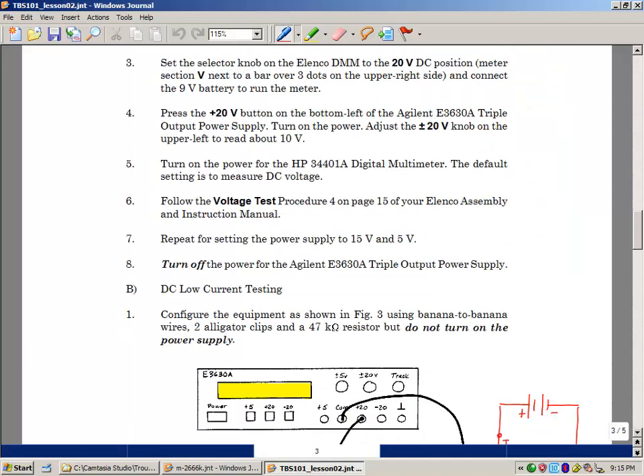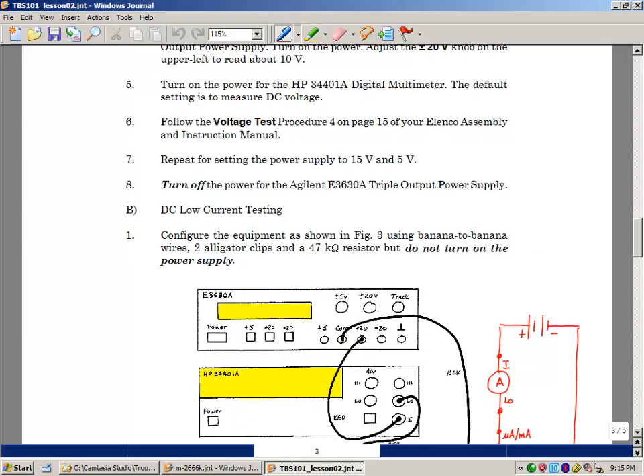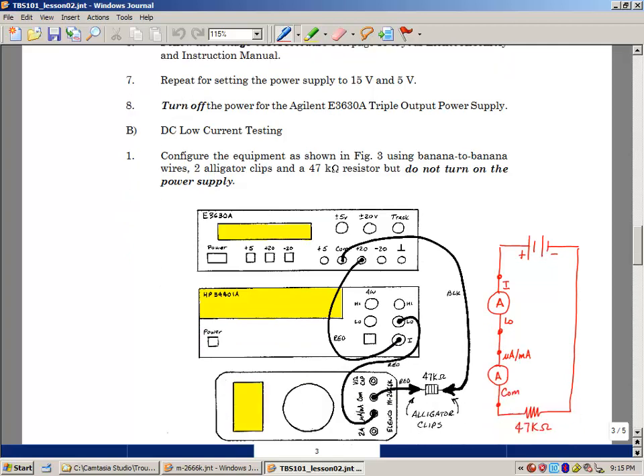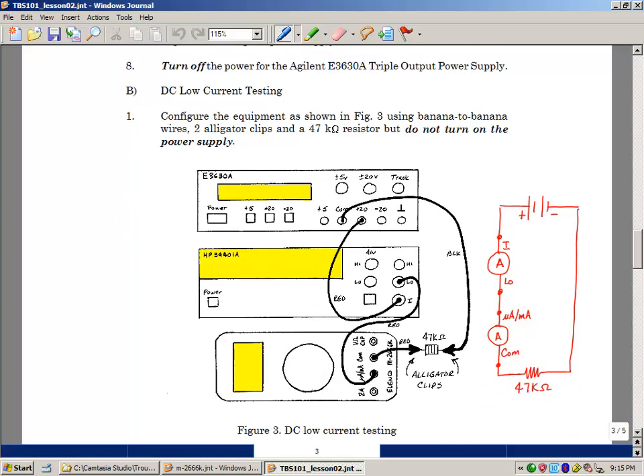In the next section, also on page 15 of your paper copy of the manual, is a series of tests for checking the current scales on the digital multimeter. If you set up the voltmeter correctly, you don't need to do any more adjustment for the current meter, but we want to verify that the meter works on all of its scales. In this particular case, we're going to hook up the DC power supply with an ammeter in series with another ammeter through resistance. The voltmeter looks like an open circuit when you connect it across something. In other words, it has no effect.